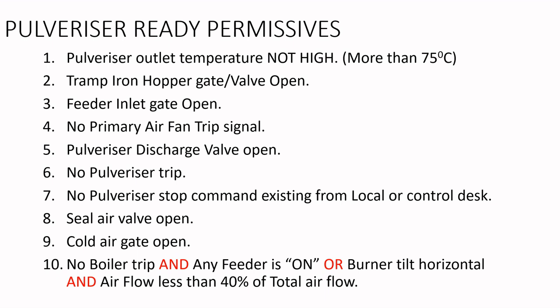Pulverizer discharge valve should be open. No pulverizer trip command should be existing. And no pulverizer stop command existing from local or control desk. Now this may be in case of maybe some oil supply is not there or something. That type of stop command should not be there from the local or control desk. Then the seal air valve should be open. The cold air gate of the pulverizer should be open.